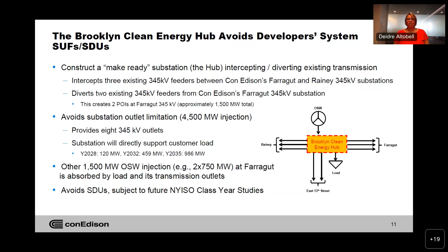up to 4,500 megawatts of injections from large offshore wind projects can easily be disseminated throughout the system to Rainey, Farragut, and East 13th Street stations to supply customer load. As previously mentioned, the hub is also designed to connect load-serving stations, so supply output from offshore wind will be absorbed by load connected to the hub. The connected load is expected to grow to close to 1,000 megawatts by 2035. So the combination of directly serving load and also being tied to the 8 outlet feeders with significant load behind them exemplifies why the Brooklyn hub will avoid the need for system-wide SUFs and SDUs.